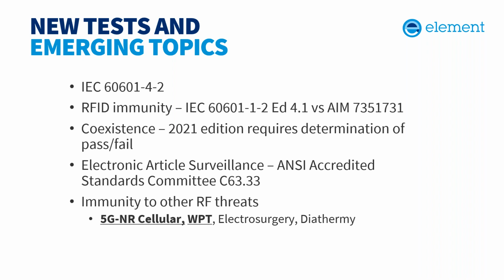And then coexistence, I just covered it, but in the past, the FDA was focused on what was in Annex A, which is Wi-Fi, Bluetooth, and DECT, those 3 radios, which have detailed requirements. But now we're seeing everybody needs to be evaluated, either through risk analysis or testing, for any type of radio. So RFID, inductive, anything needs at least some sort of evaluation. Additionally, the FCC is starting to look at electronic article surveillance testing, so it's something we're seeing requests for, even though there's no standard out there. A standard is in development, and I'm on the working group for that, and the final draft is in progress.